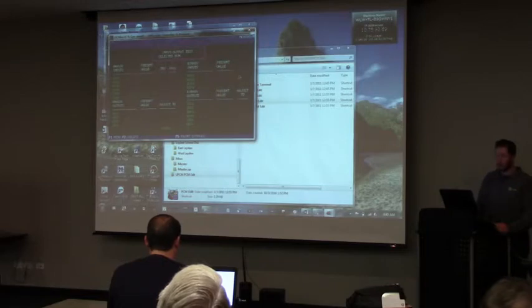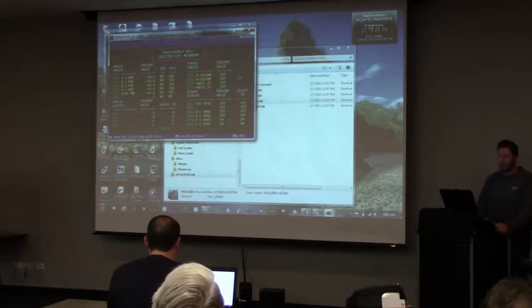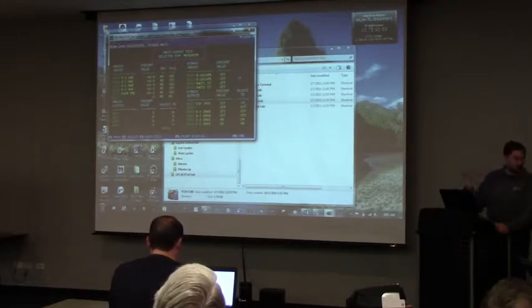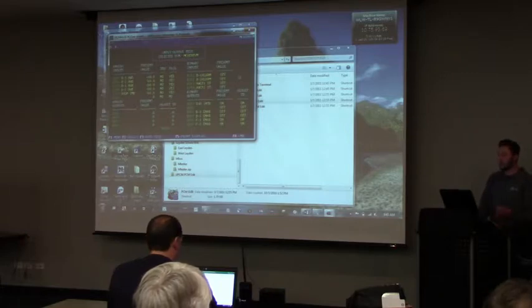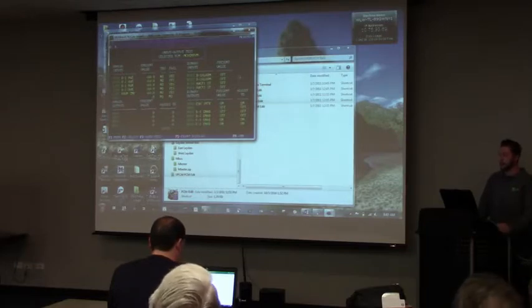Just hit Y, and then once it uploads everything here, you can just hit the down arrow and change, like, the exhaust to on. And then you just hit enter. Then it's downloading it, download successful, please wait. And it actually just turned the binary output on right now. So it helps you troubleshoot stuff if you ever get in a pinch, to use this test mode to test the points, analog outputs, and binary outputs. It definitely does help out. So I can put that back to off.